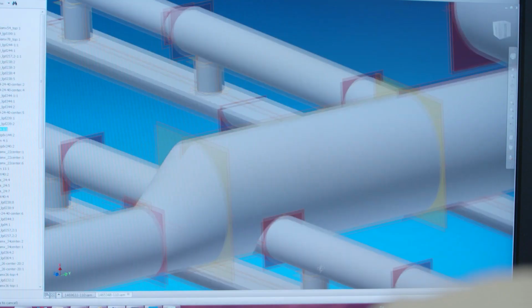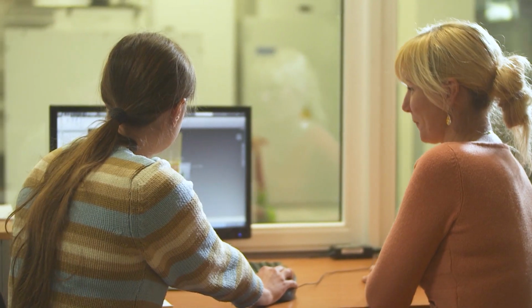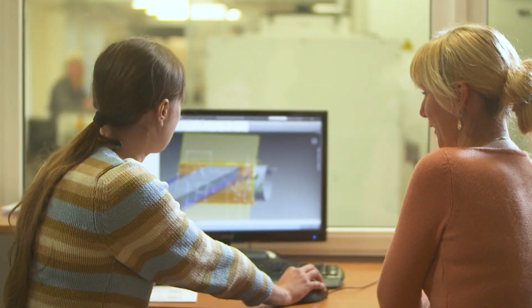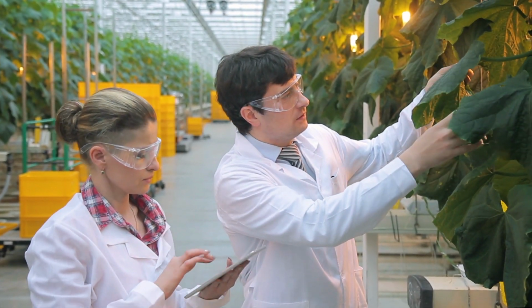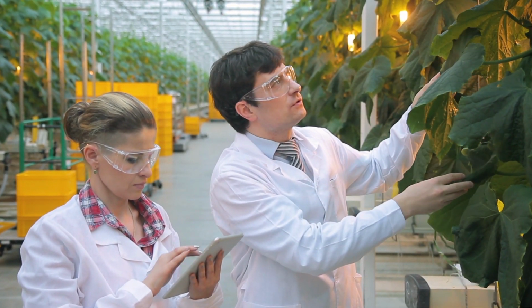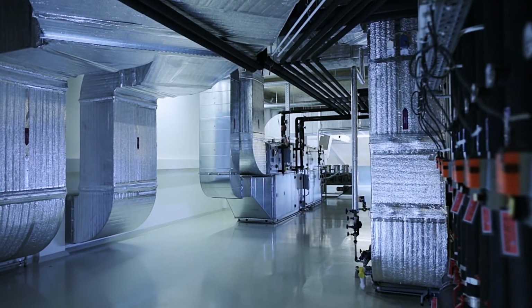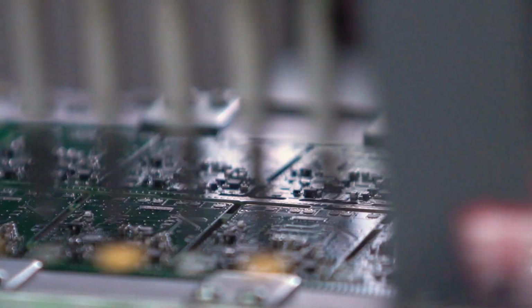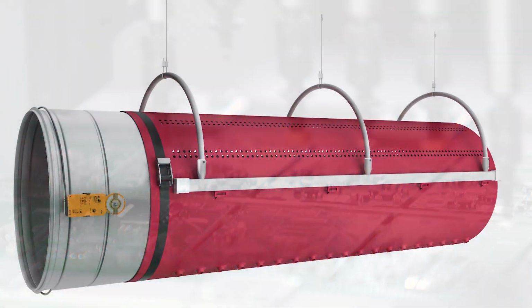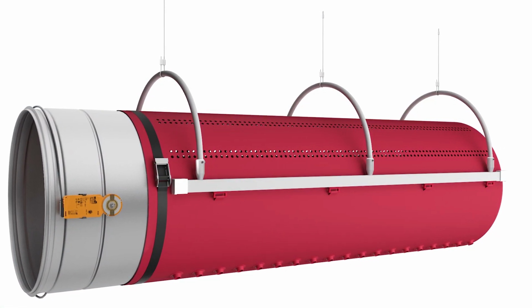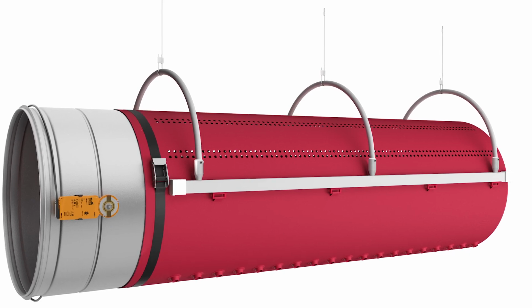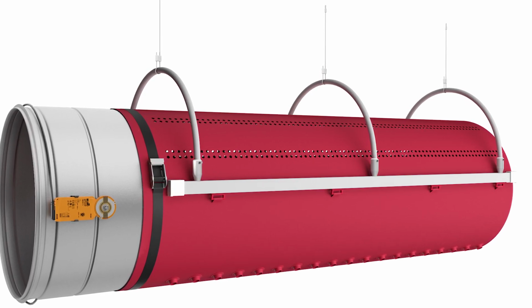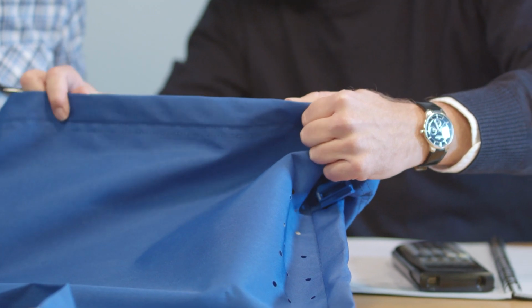When using conventional air dispersion solutions, engineers typically address this challenge by optimizing the flow patterns for average conditions where the delta T is less extreme, or by using an expensive type of diffuser or nozzle that can be adjusted using costly electronics. By combining two air dispersion systems in one duct, the Fabric Air VarioDuct efficiently solves the challenge. It allows our engineers to combine the optimum airflow for heating as well as cooling in the same duct.